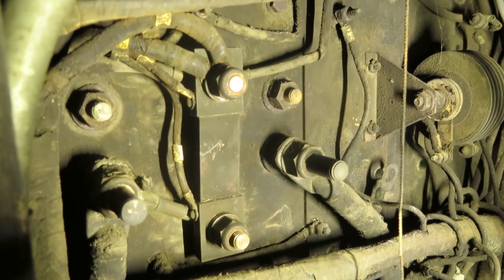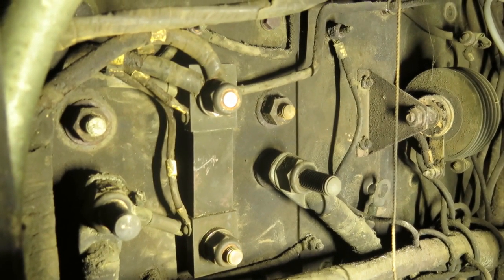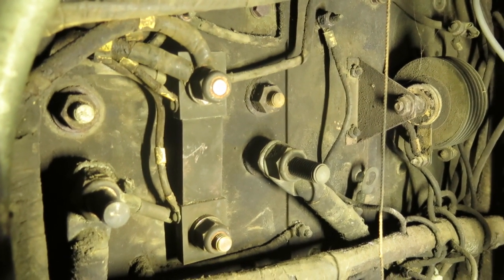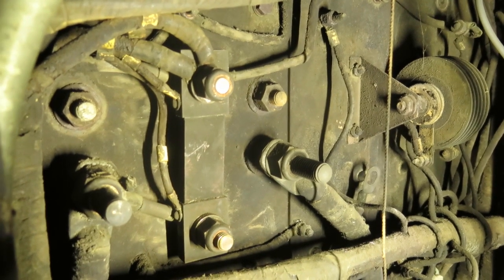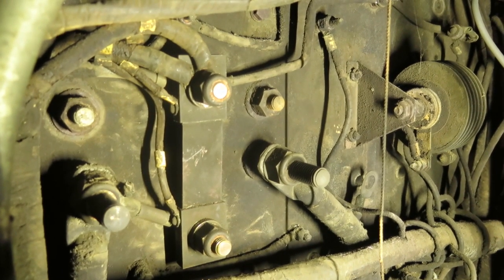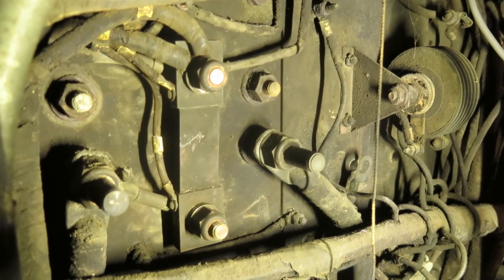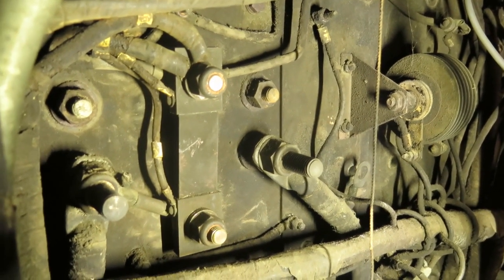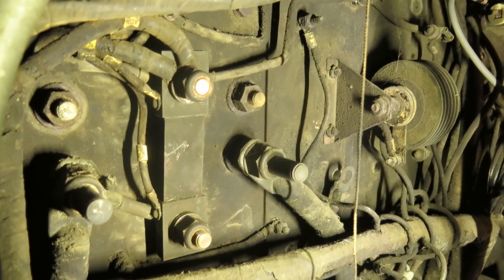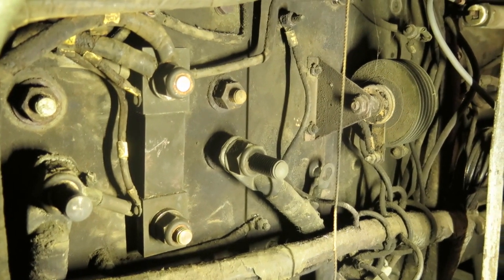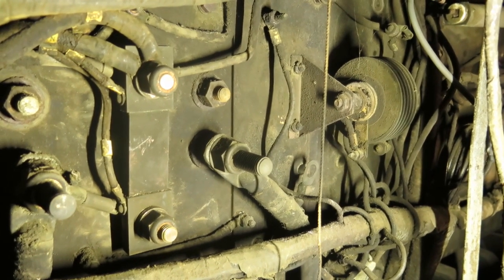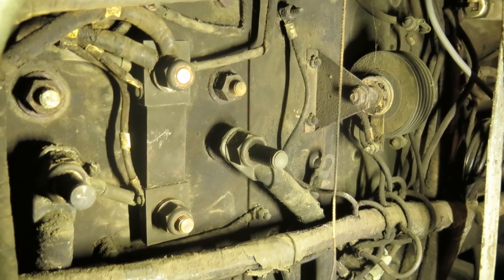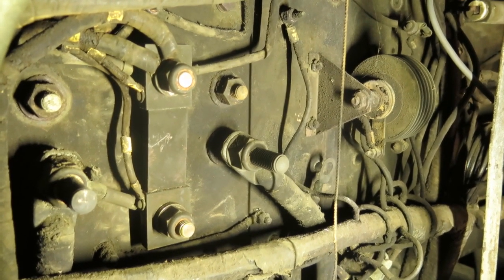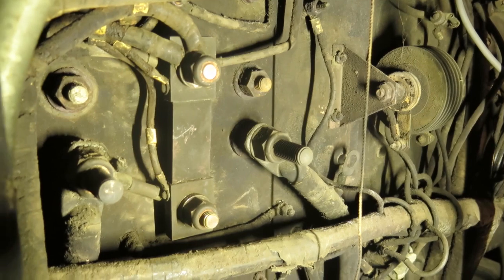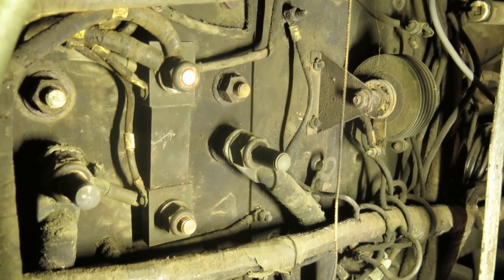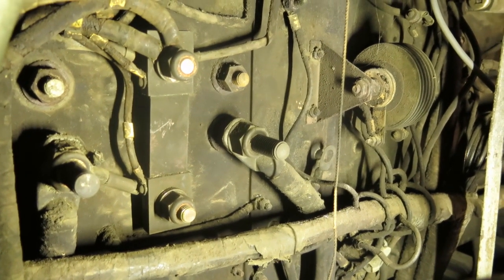I took that loose and started pulling wires apart, and fortunately the ground was not in the auxiliary generator. It wasn't in the battery field circuit of the main generator either, both of which would have been a real expensive challenge. It headed toward the load regulator circuit, the battery field cabling that goes to the load regulator, and then comes back and goes into the battery field for the generator and makes the locomotive generator do its thing.